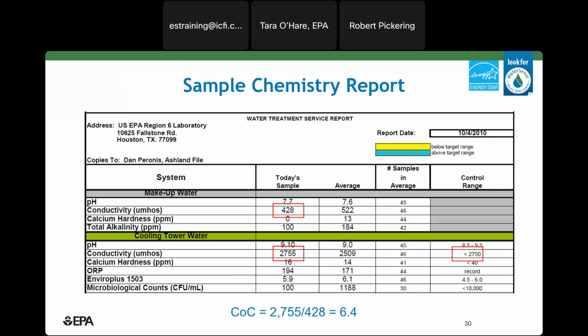So this is an excerpt from a pretty typical water treatment report. The format of these reports can differ a little bit depending on the vendor, but the information is usually the same. And often the more information you get, the better. So the report includes conductivity on the makeup water and the cooling tower water. This cooling tower water is the same as the blowdown water that gets sent to the sewer.